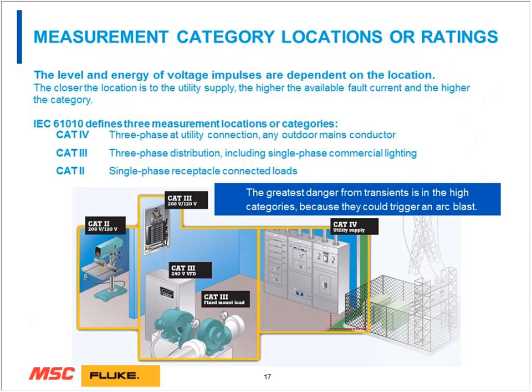So here we have measurement categories, locations, or ratings, category 2, 3, and 4. In this one, you can see that the greatest danger from transients is where we're measuring at the service entrance, or at the SE to the building, and that's on the secondary side of the transformer. Again, our instruments measure up to 1,000 volts, which by utility standards are considered to be low voltage, still a lot of voltage. At the utility entrance, at the service entrance, that is where you're going to find the greatest amount of current that could cause this arc flashing incident.